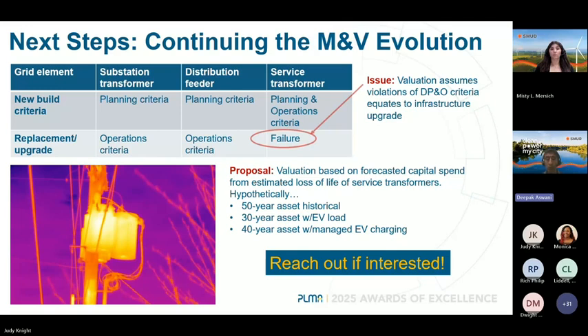As a result, most utilities, including SMUD, do not replace service transformers proactively upon overload. Rather, they continue to run to failure. That means avoiding overload of service transformers does not directly translate to a reduction in capital spend.